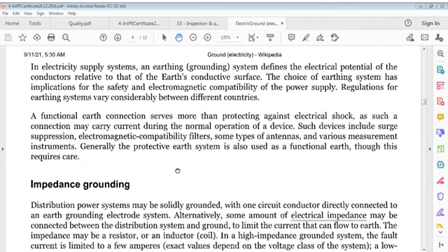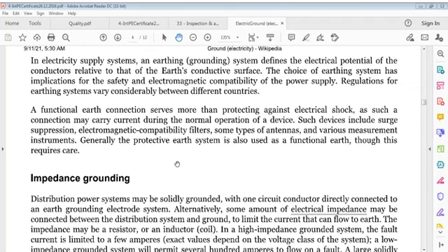Earthing systems. In electricity supply systems, an earthing or grounding system defines the electrical potential of conductors relative to that of Earth's conductive surface. The choice of earthing system has implications for safety and electromagnetic compatibility of the power supply. Regulations for earthing systems vary considerably between different countries.